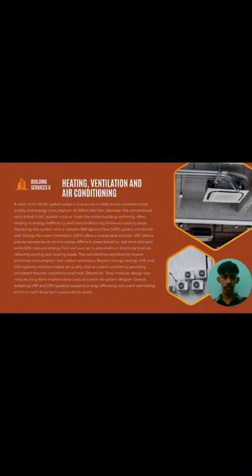VRF allows precise temperature control across different zones based on real-time demand, while ERV recovers energy from exhaust air to precondition incoming fresh air, reducing cooling and heating loads. This combination significantly lowers electricity consumption and carbon emissions.